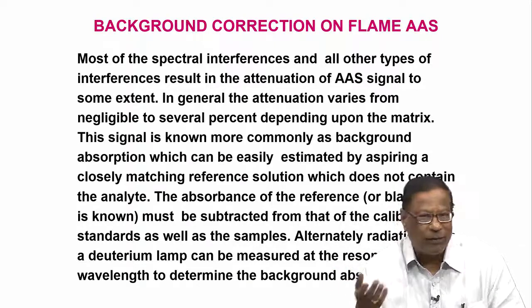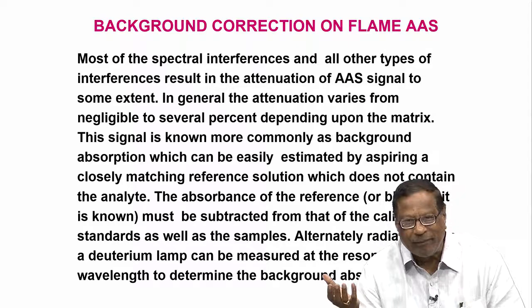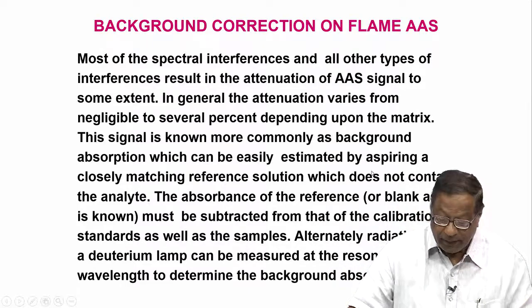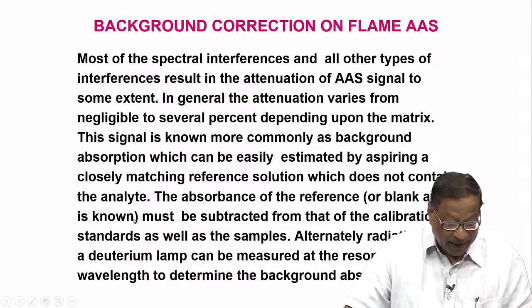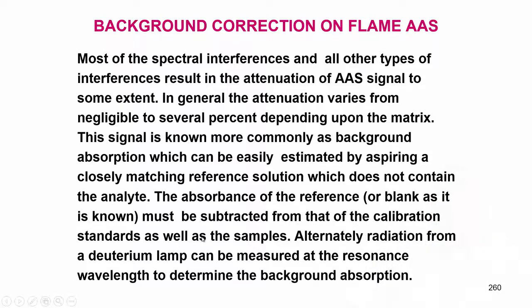That means we are aspirating a solution which contains water as the blank. If there are extraneous elements, we try to match the extraneous elements apart from the analyte — that becomes the matrix solution. The absorbance of the reference or blank must be subtracted from that of the calibration standard as well as the samples, because in the blank there will be some amount of absorbance — molecular absorbance, spectral interference, whatever it is — and that needs to be subtracted to get the correct analytical result.